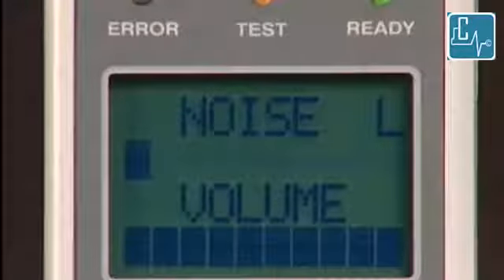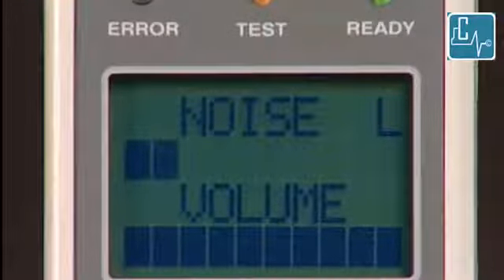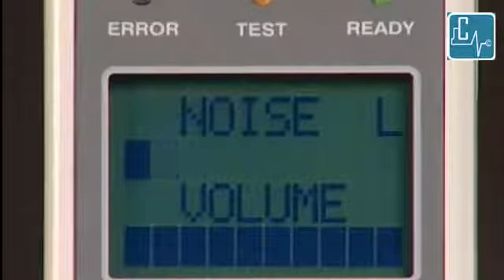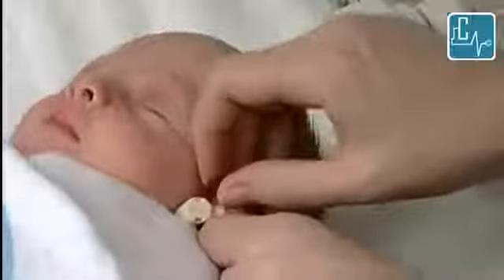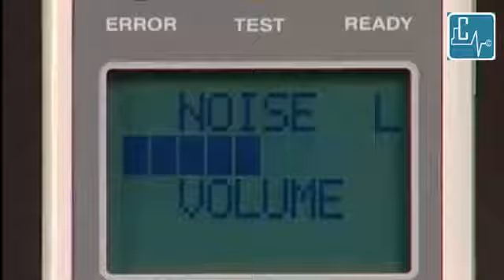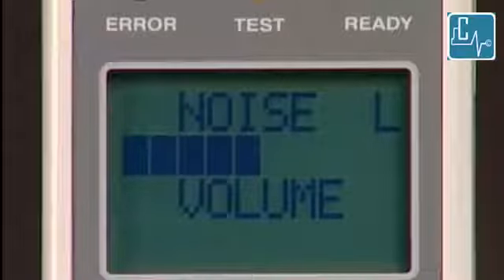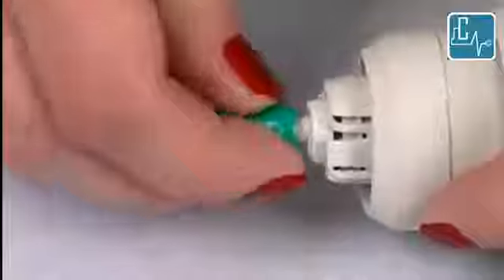If either bar does not move to the left of the screen, then a problem exists. If the volume bar will not move to the left, then a proper seal has not been obtained. To fix this problem, try repositioning the probe or selecting a different ear tip. If no volume bar is shown, the probe may be resting against the ear canal, or a piece of debris such as cerumen or vernix is present. To fix this problem, try repositioning the probe, replacing the ear tip, or checking for debris in the probe.